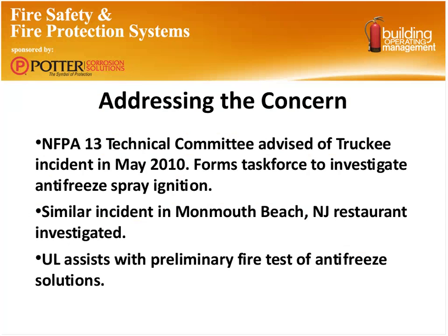This falls under the NFPA 13 Technical Committee, who started the investigation in May of 2010. What they found, when they started looking through the fire records of the different fire departments, was a similar incident at a restaurant in Monmouth Beach, New Jersey. What happened in this case? Well, a patio heater was a little too close to the overhang in a building, and it set off the exterior sprinklers, which were freeze protected for this canopy area.